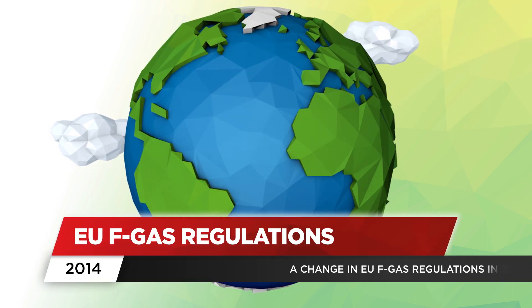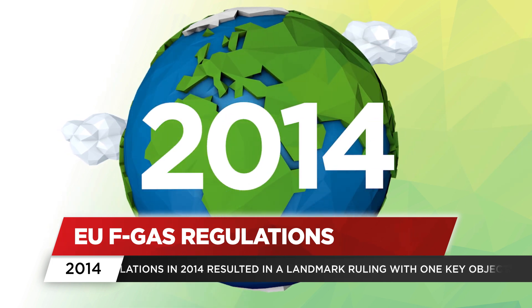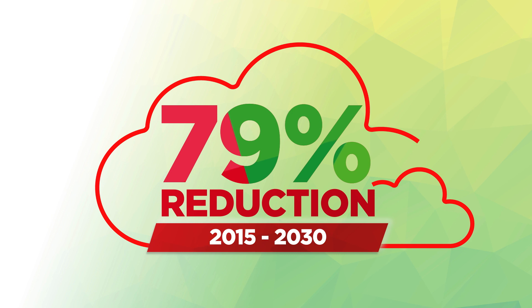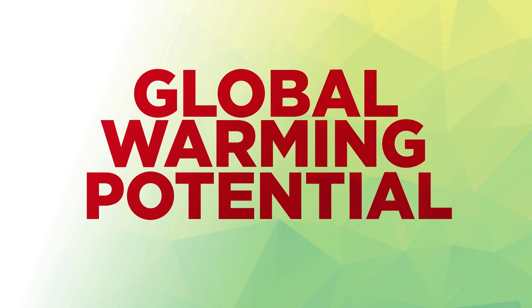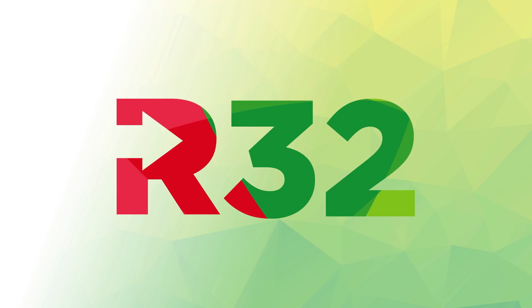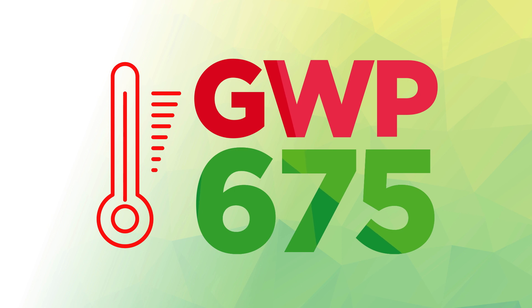It was all to do with a change in EU F-gas regulations, with a landmark ruling in 2014 having one key objective: to reduce F-gas emissions by 79% between 2015 and 2030, by cutting the availability of hydrofluorocarbons with a high global warming potential, or GWP. Part of this green commitment has been a switch from traditional refrigerants to R32, which with a GWP of 675 — one-third that of R410A refrigerant — is both highly energy efficient and better for the environment.